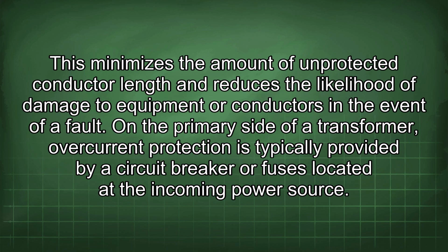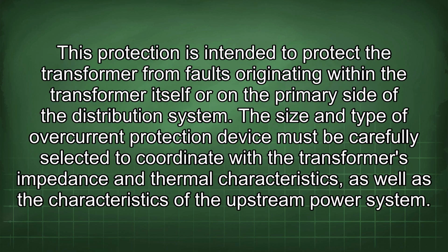This minimizes the amount of unprotected conductor length and reduces the likelihood of damage to equipment or conductors in the event of a fault. On the primary side of a transformer, overcurrent protection is typically provided by a circuit breaker or fuses located at the incoming power source. This protection is intended to protect the transformer from faults originating within the transformer itself or on the primary side of the distribution system. The size and type of overcurrent protection device must be carefully selected to coordinate with the transformer's impedance and thermal characteristics, as well as the characteristics of the upstream power system.